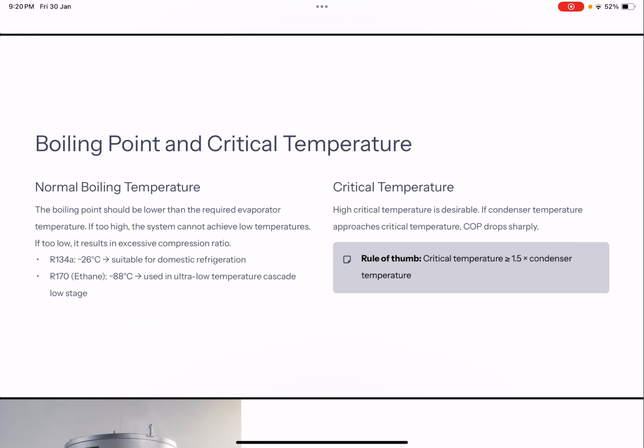You can imagine that if you have a low critical temperature, then the spacing between the critical temperature and the condensation temperature would be much less. So as a rule of thumb, the critical temperature has to be greater than 1.5 times that of the condenser temperature. It means that the critical temperature has to be high so that the COP is much better. If you have a lower critical temperature, the COP would drop sharply. It means that if the condenser temperature approaches the critical temperature, then the COP would be much lower.